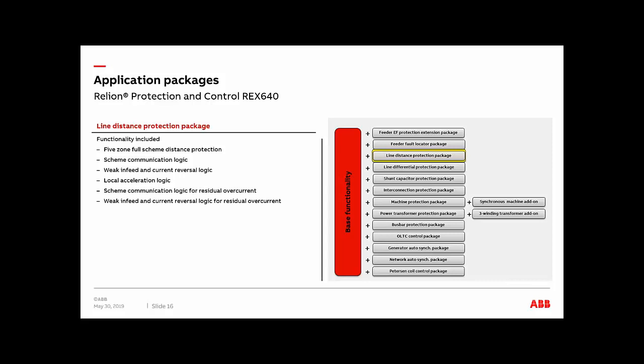Then moving on to the line distance protection package. This package will give you 5 zones of protection for distance. It is important to mention here that we're going to have 5 zones of protection, and it will give you a scheme of communication logic, which you can use for step distance protection. The 5 communication schemes that are supported for this relay are the direct underreaching transfer trip, DUTT, permissive underreaching transfer trip, PUTT, permissive overreaching transfer trip, POTT, directional comparison blocking scheme, DCB, and directional comparison unblocking scheme, DCUB. This is going to be your 5 scheme communication logic that you can implement.